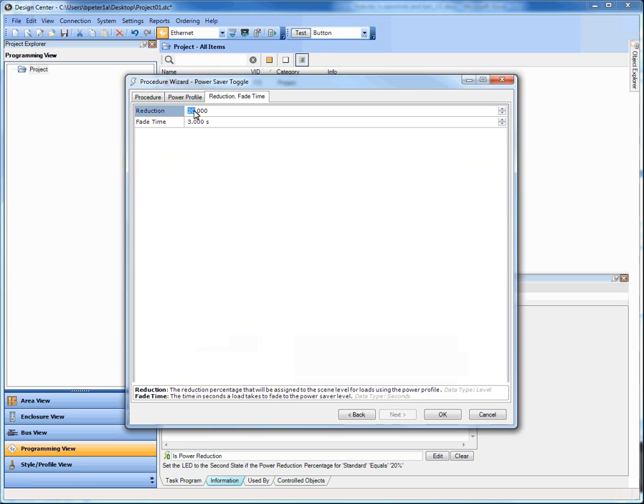I go to my tab and look at the reduction and the fade time. What I'm doing is typing in a percentage value to reduce all of the loads that use that power profile by. So if I type in 20% and give it a fade time of 3 seconds, or 5 or 10 seconds, what's going to happen is: all the loads currently on that are above the reduction level will go down to that new level. So if a light was on at 95%, it's going to go down to 75% — actually 75% of the 97% max set up in the power profile — and it'll do it over the fade time of 3 seconds.